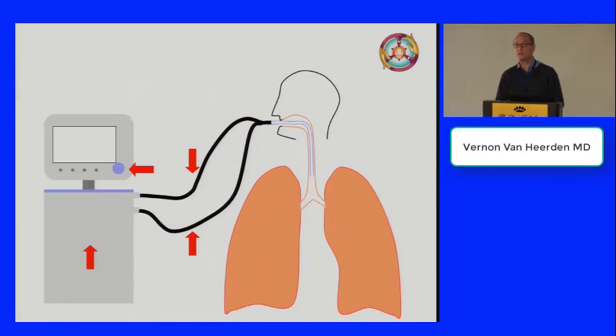Okay, so then we need to decide, if we have the high airway pressure alarm, whether it's a ventilator problem or a patient problem. If you're looking at the ventilator or equipment side of the equation, it could be inappropriate settings, inappropriate measurement of the pressure, or a problem with the tubing. You've got a kink in the tubing, you've got too much water in the trap, which is causing blockage. You haven't changed the filter in a couple of days, and it's all clogged up. All of these can cause high airway pressures. Or it could be a patient problem, and we'll come to some of those in a moment, which can be causing the high airway pressures. And the problem is to differentiate between the two and to treat appropriately.